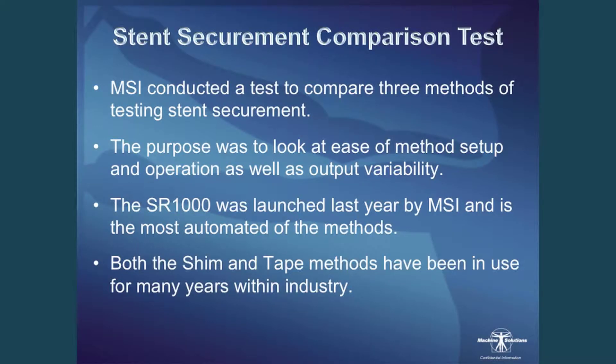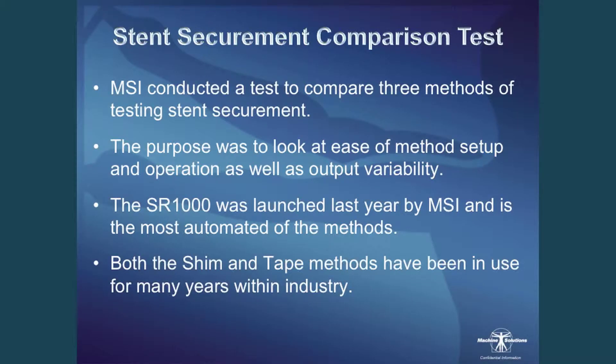The comparison test: what we did at MSI was conduct a test to compare three methods of stent securement testing — the SHIM method, the Tape method, and MSI's SR1000. The purpose was to look at ease of method setup, ease of operation, as well as output variability. The SR1000 was launched last year by MSI and is the most automated of the methods. Both the SHIM and Tape methods have been in use for many years within the industry and are currently in use today.